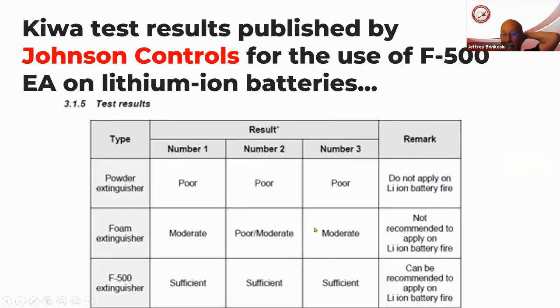And the reason I want to bring that up is because as we look at the results from the Kiwa tests and the Johnson Control test on the batteries: when they tested the powders, they found powders do not work on lithium-ion batteries, don't apply. When they tested the foams, they gave them moderate to poor, but again recommended not to apply on a lithium-ion battery fire, it's not very beneficial. But the F500, in all the tests they ran, was sufficient and can be used on these lithium-ion battery fires.